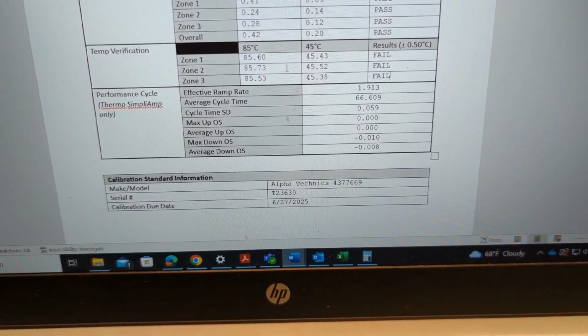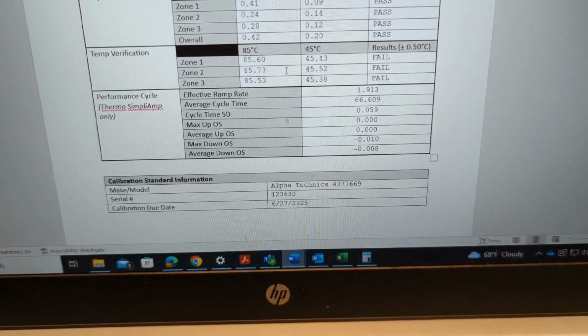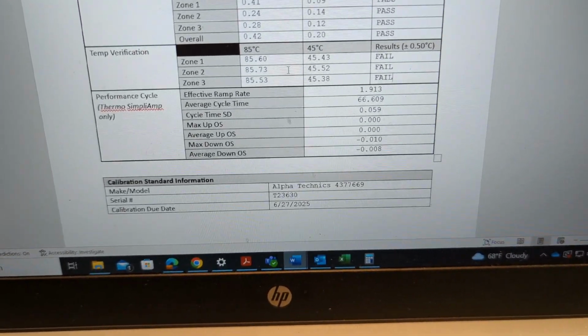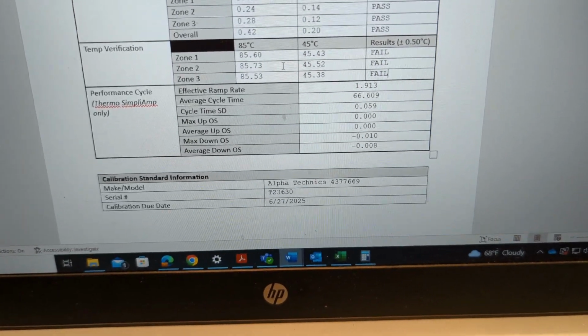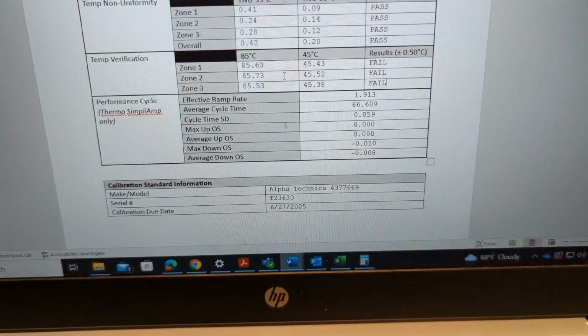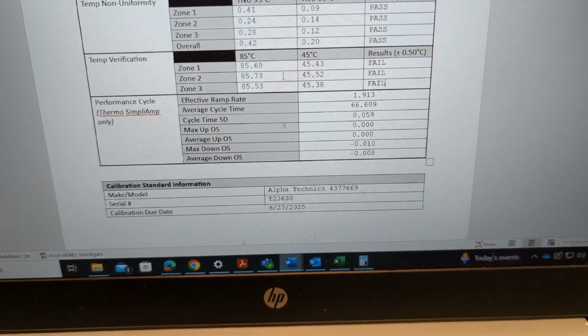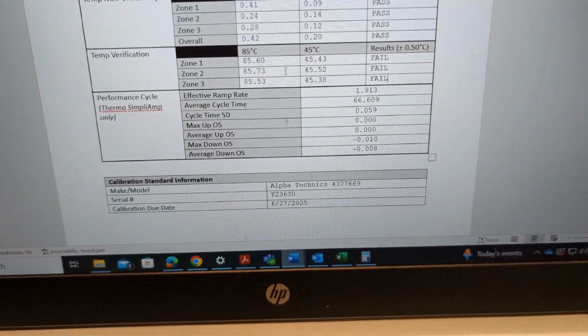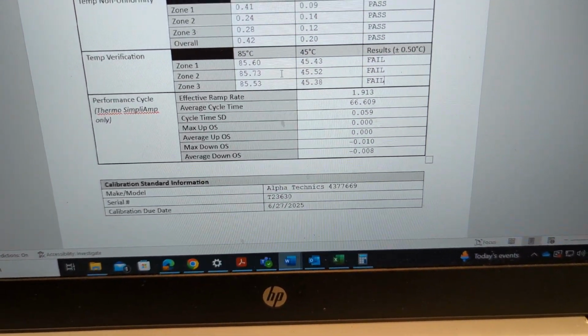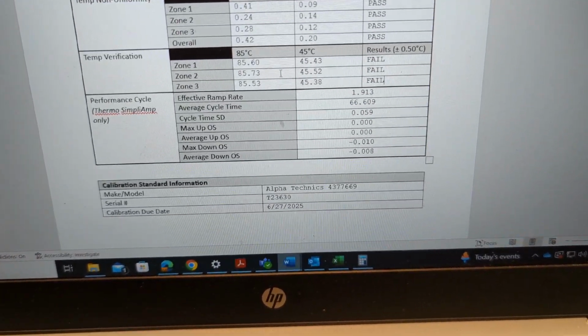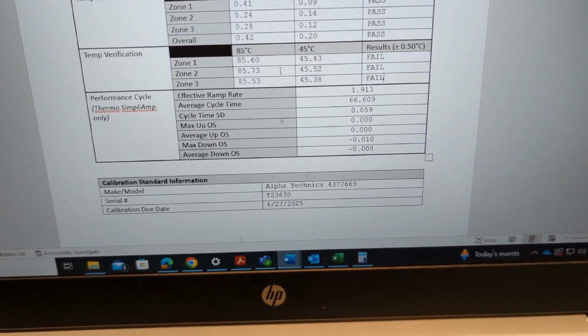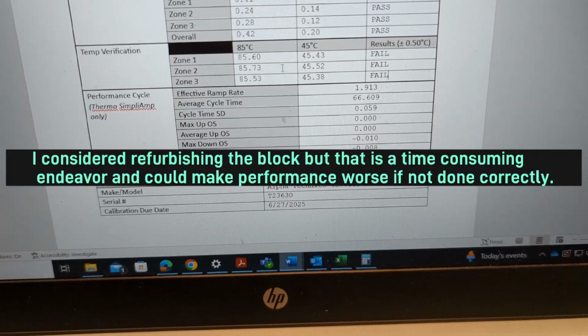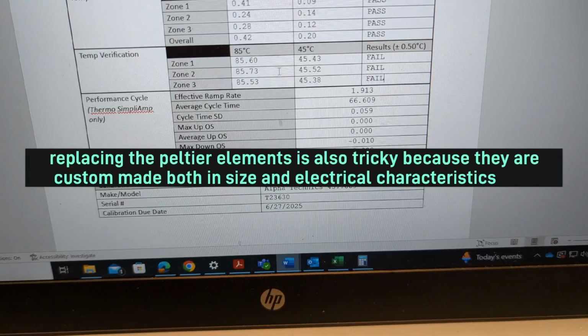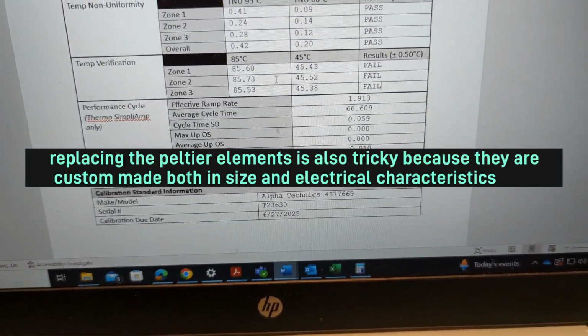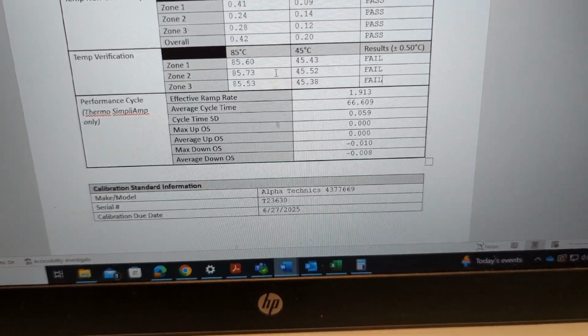And I've always thought it's probably due to the fact that they're not dissipating heat properly. They do use Peltier elements that are on a big heat sink, and maybe they're attached via some thermally conductive paste or adhesive, and maybe that is starting to break down due to constant cycling of the temperature, and they're not able to dissipate heat as well. That's kind of what I always thought was going on. It could be that the Peltier elements themselves are just starting to break down, but I was always curious if there was a way to resolve this without replacing parts.